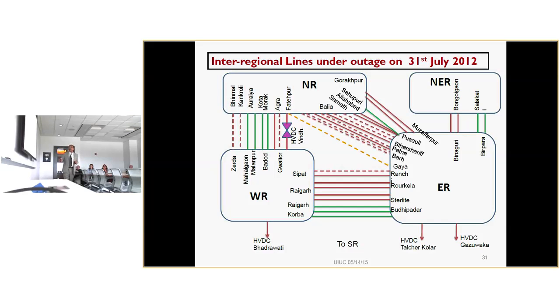And since western has a lot of thermal generators, they faced a deficit of power. Eastern had a surplus, but looking at the demand of the northern region, there was a deficit of power. There were oscillations between northern, eastern, and northeastern. So one by one, these lines tripped, and northern got separated from eastern. Their generators tripped on over frequency. So on the second day, northern, northeastern, and the majority of the eastern region were under blackout.